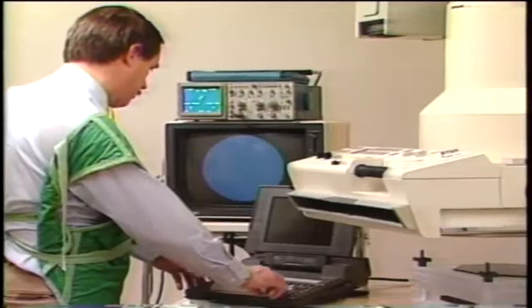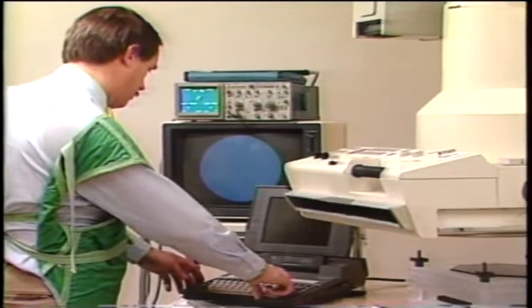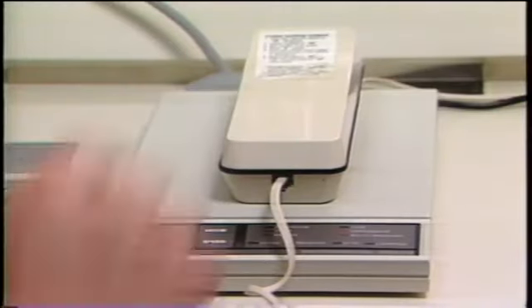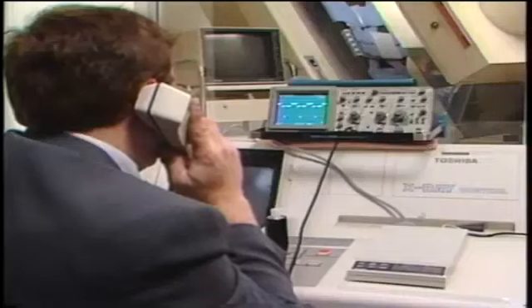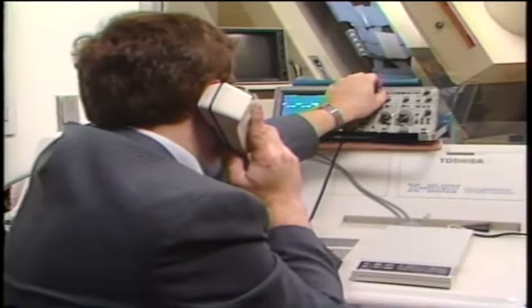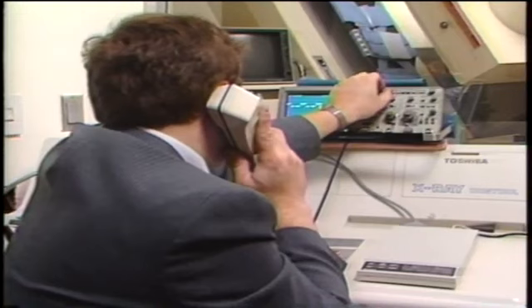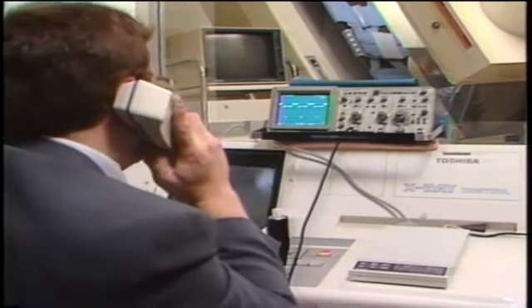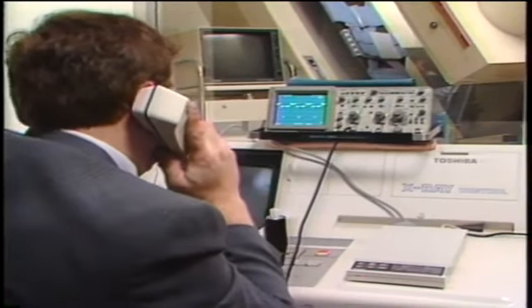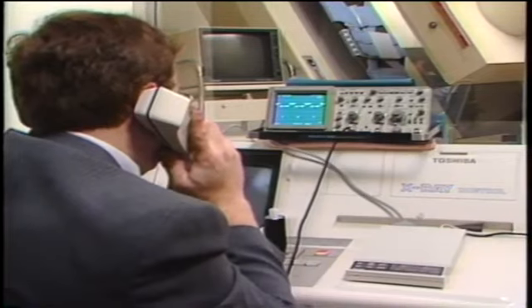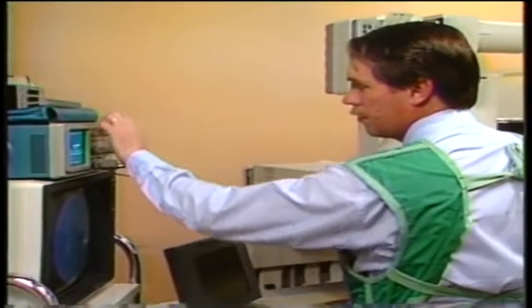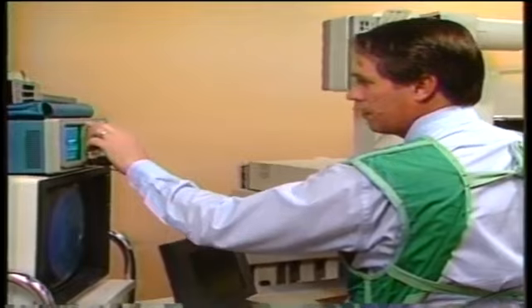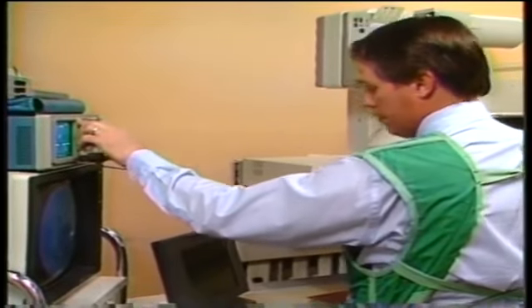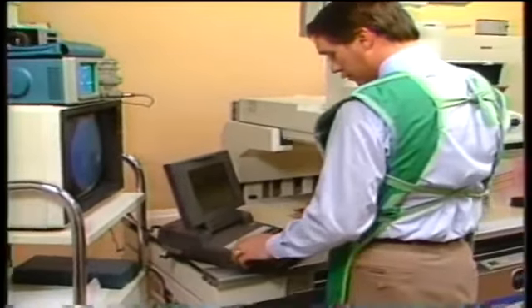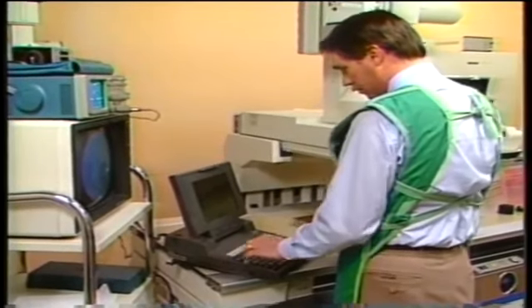The communications options can also provide waveform data to your personal computer or other controller, either directly or over a phone line through a modem. Either the GPIB option, option 10, or the RS-232 option, option 12, provide waveform transfer to or from reference memories or displays, instrument control of storage acquisition modes, and single sweep reset. In the 2230, the communications options also provide extended battery-backed memory.